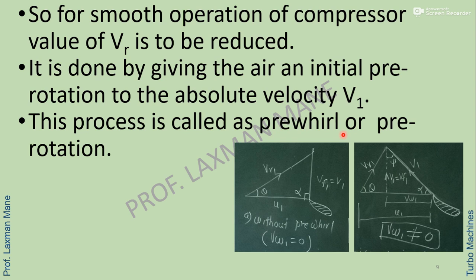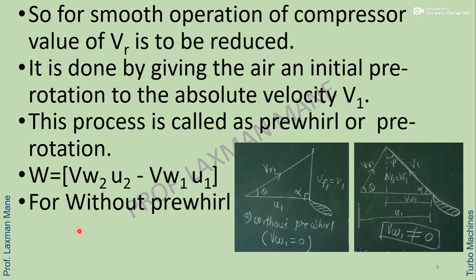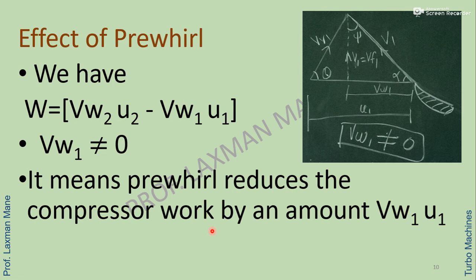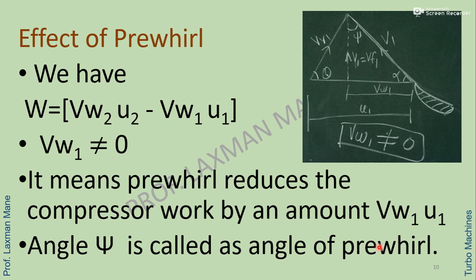This process is called pre-whirl or pre-rotation. For this case, work done = vw2 × u2 − vw1 × u1, because vw1 is not equal to zero. Without pre-whirl, vw1 = 0 and work = vw2 × u2. The effect of pre-whirl is that it reduces compressor work by an amount vw1 × u1. The angle psi in the diagram is called the angle of pre-whirl.